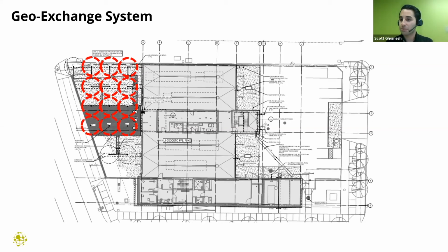There's no backup heating in this building at all, no backup boilers, no backup cooling towers or anything. The Geo-Exchange field, in order to meet 100% of the heating and cooling needs for this building, takes up just a small portion of the site in the top left corner.